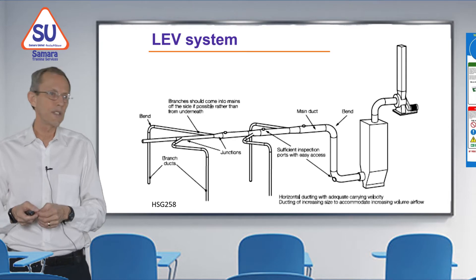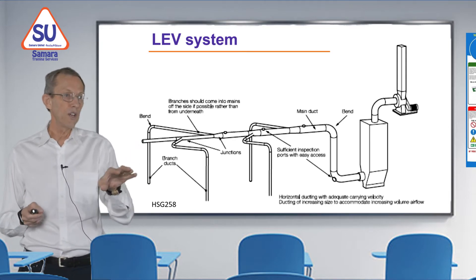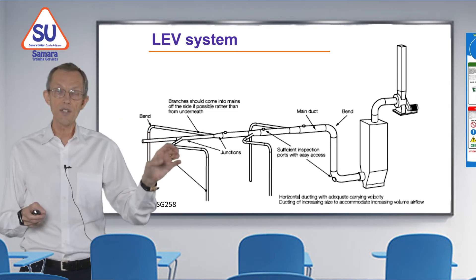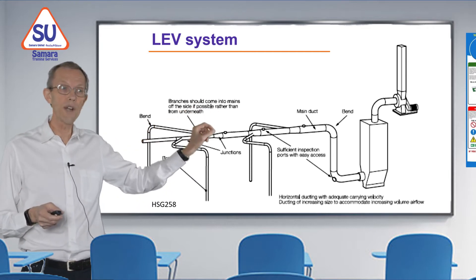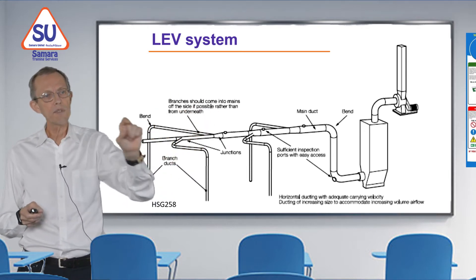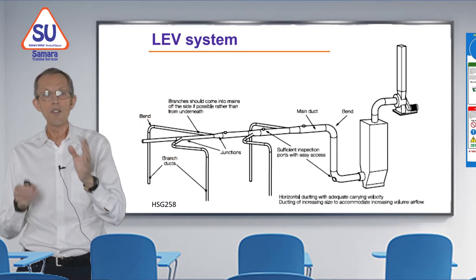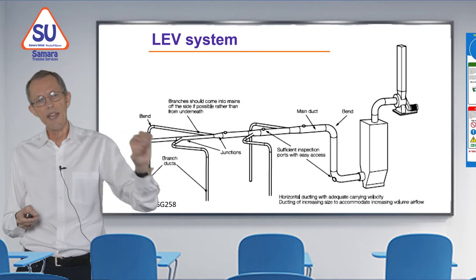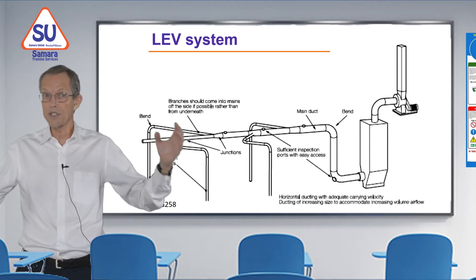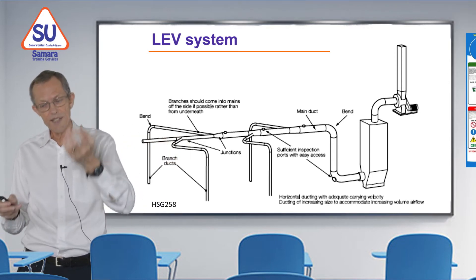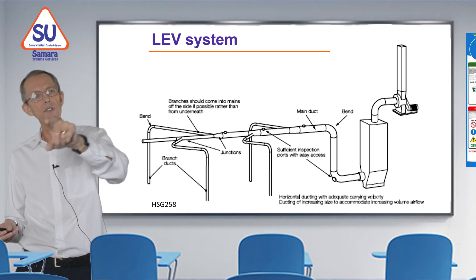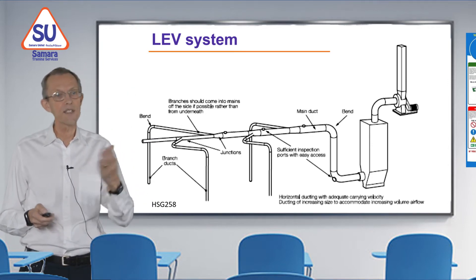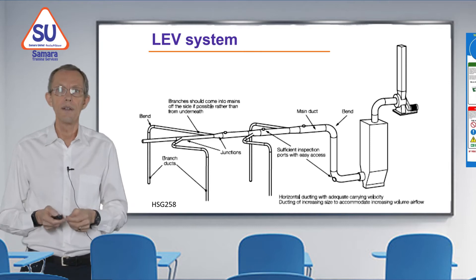A slightly more complicated system shows four different branches, each with hoods at the end of vertical pipes. The main pipe goes on to a bigger system, and all these pipes come down to the central duct and into the air cleaner. In this case it's not a filter — the air comes in at the bottom and rises slowly through a big pipe, so the dust settles at the bottom and the clean air goes through the air mover and is exhausted above the roof.